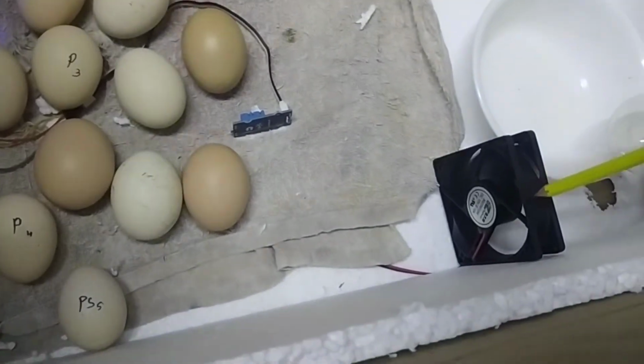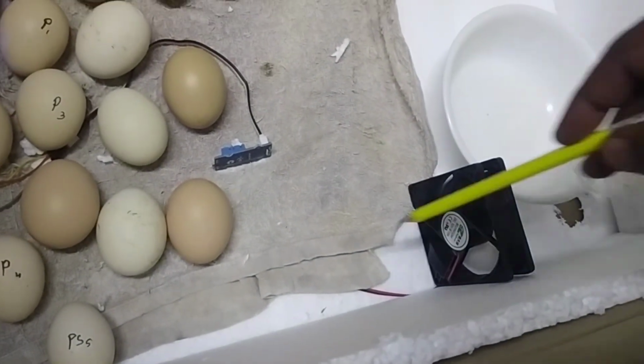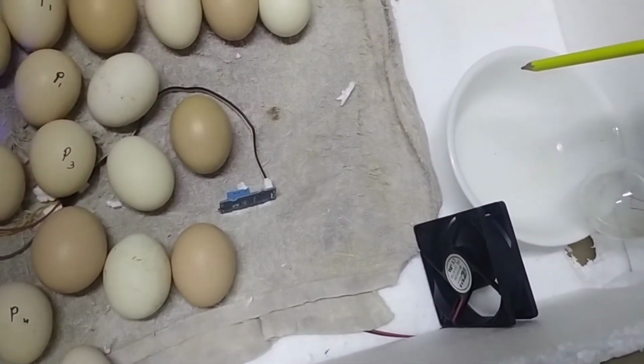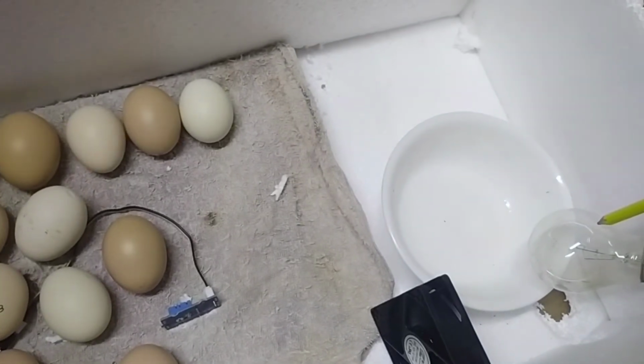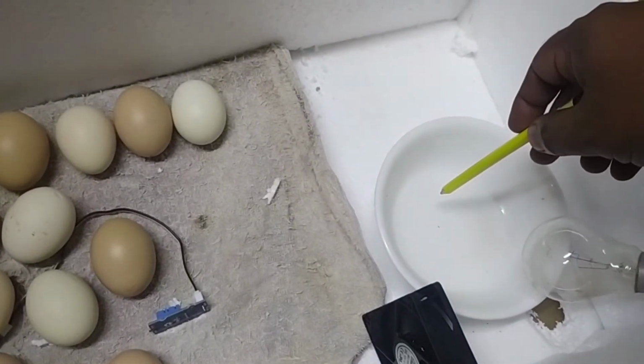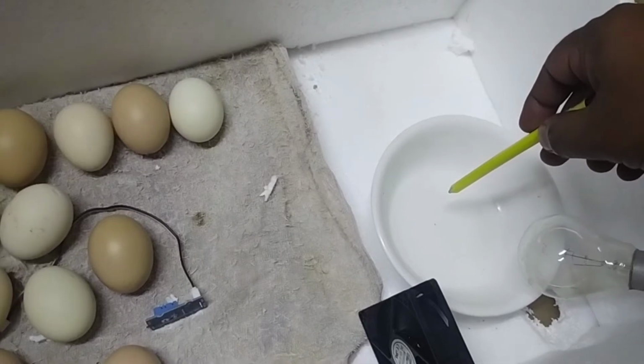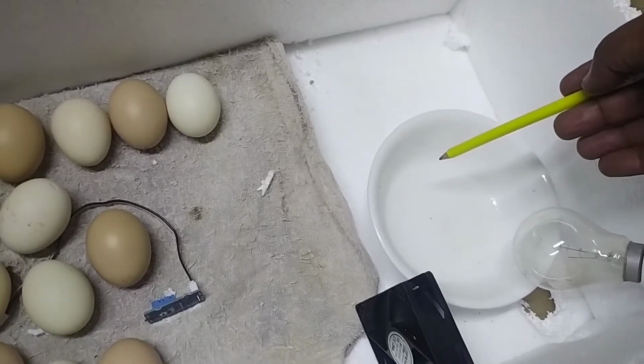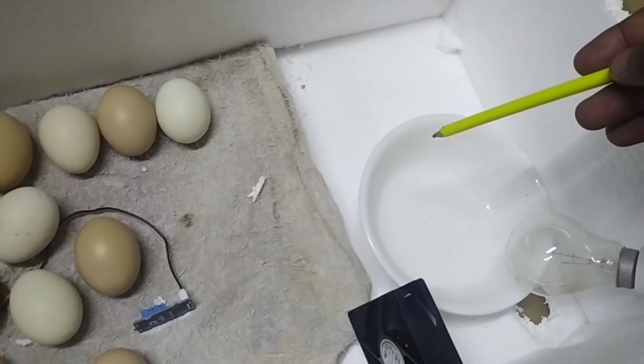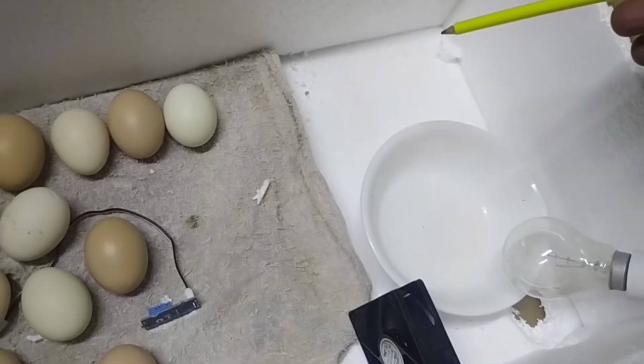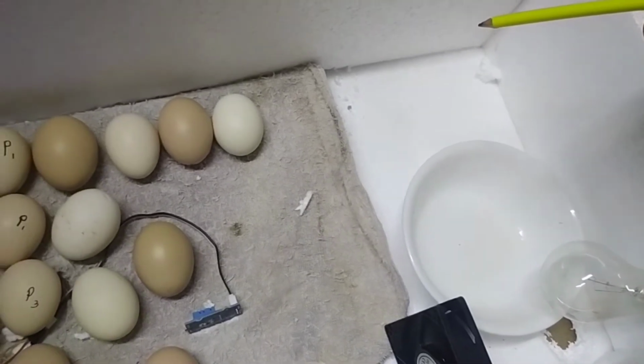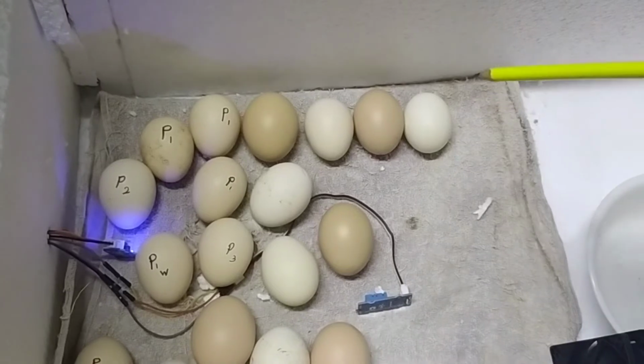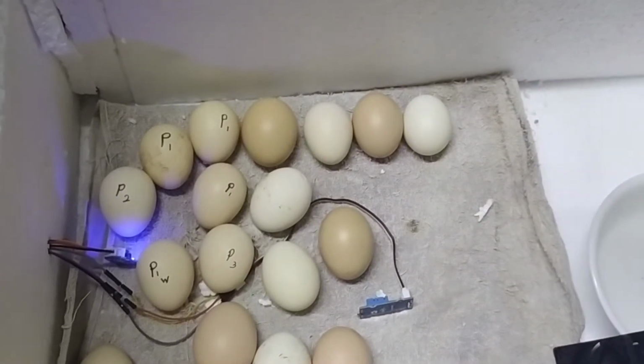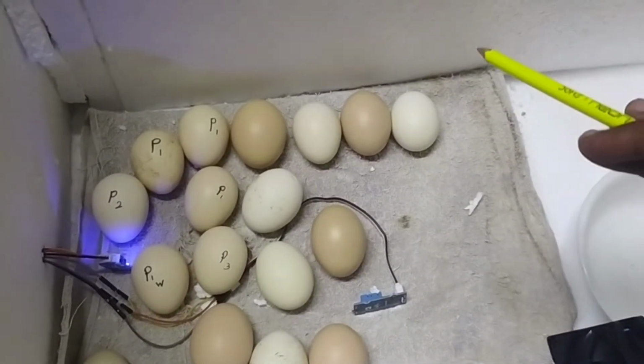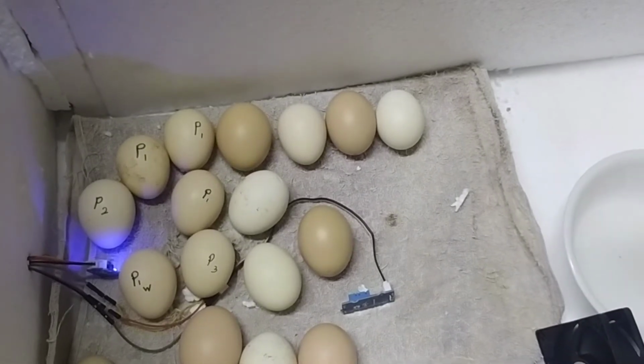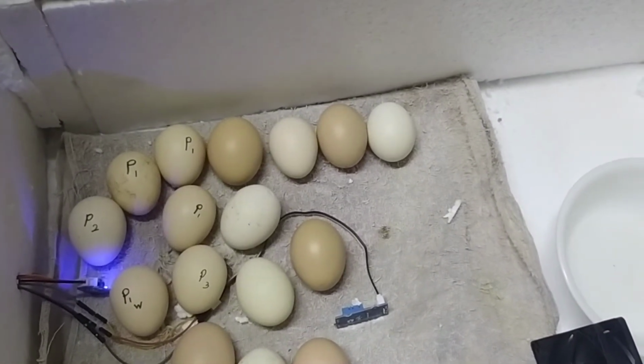Here we have a fan, and that's a rotating fan that's used to circulate air within the incubator. We have an incandescent bulb, and then we have a bowl of water. A bowl of water is used so that the humidity inside can be increased to match the humidity of a chicken. So here the principle of an incubator is that the temperature that needs to be maintained in the incubator should be the same temperature as that of a chicken.